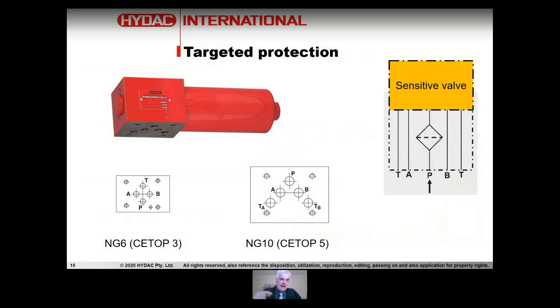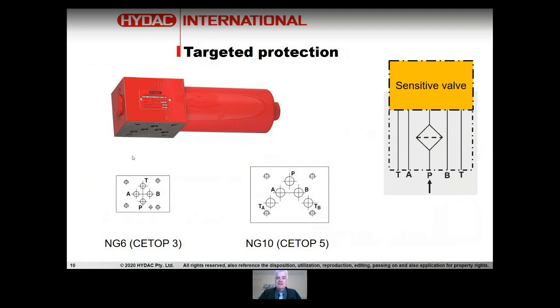You can also have targeted protection. If you have very sensitive components — say a servo valve or a proportional valve — there's an opportunity to put a filter directly in line before that component. One neat way of doing that is having a filter with an interface suited to industrial valve interfaces: NG6 Cetop 3 or NG10 Cetop 5. This is called a DFZ, and it is sometimes termed a last-chance filter. After your main filtration has occurred, anything that's gotten through will be caught here, protecting that very sensitive and sometimes expensive component.